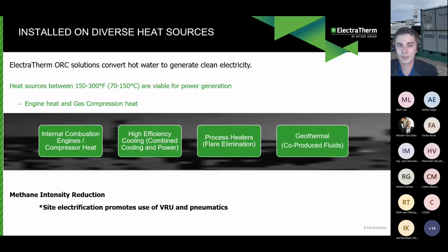Now, what that means in a nutshell is, that's how the process works, but what we're doing is converting heat to power or heat to efficiency. And emission savings or heat to power for your scope 1 emissions reductions. So heat can come from a variety of sources, particularly at midstream compression sites and all compression sites. So heat from internal combustion engines or compressor heat could be utilized for power production. High efficiency cooling, so combined cooling and power, that's where we use engine jacket water at lower temperatures than what most heat recovery is capable of.